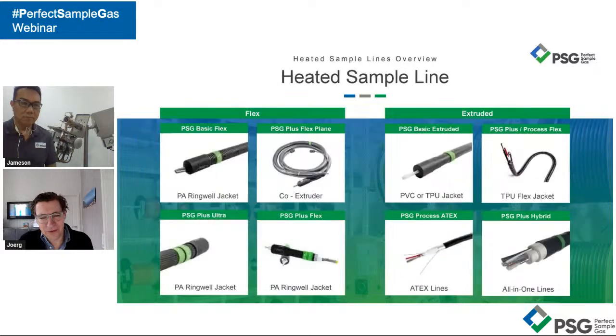Therefore, when we look at an overview of our two worlds, the so-called flex heated sample lines, the handmade heated sample lines, allow a very low bending radius on the one hand, but typically are not cut-to-length technology. The right-hand side even allows these lines to be shortened, and I think that is a pretty big advantage. What is your favorite line, Jameson?